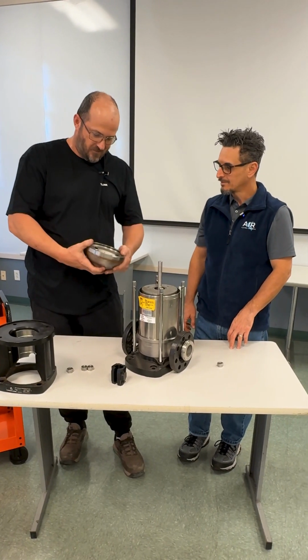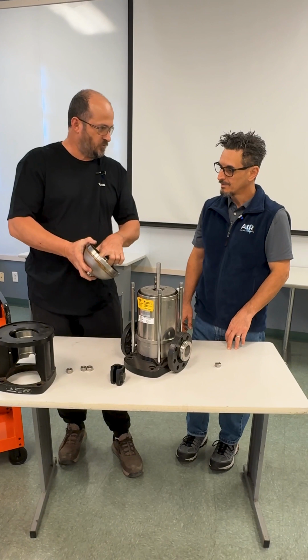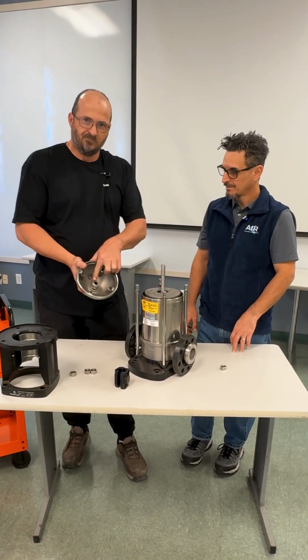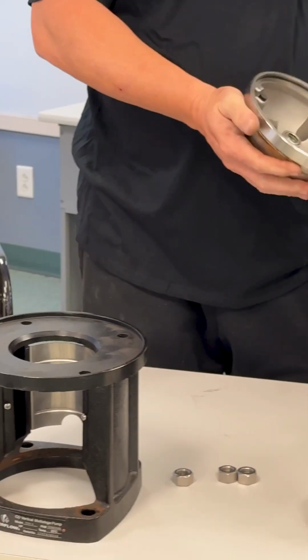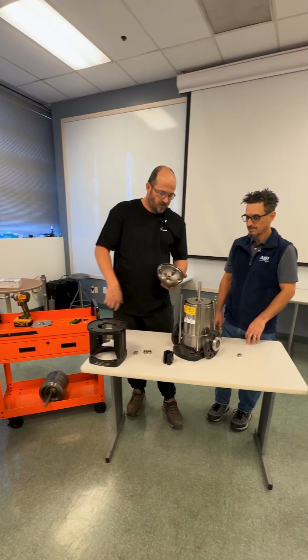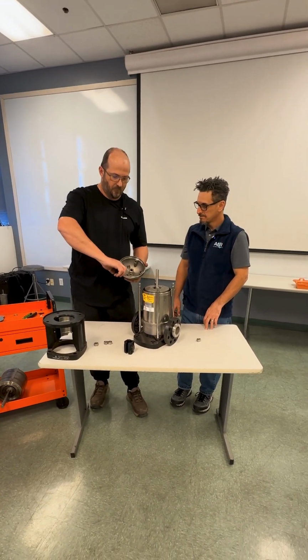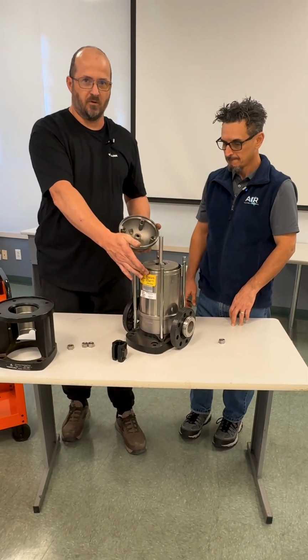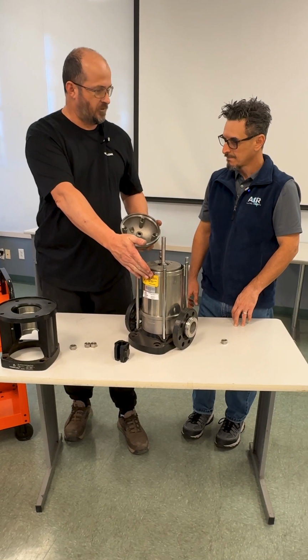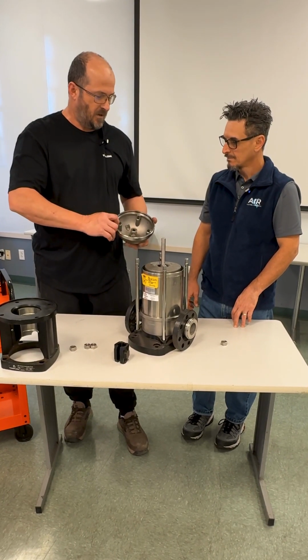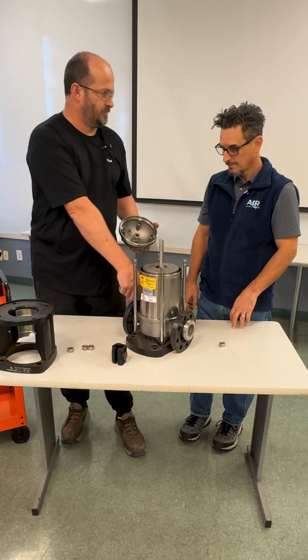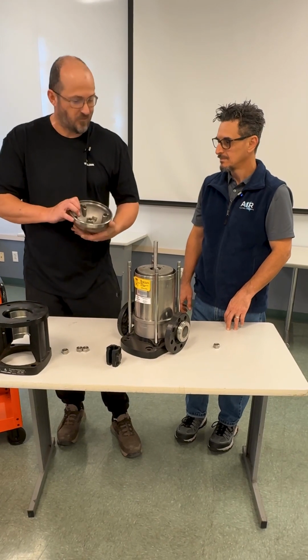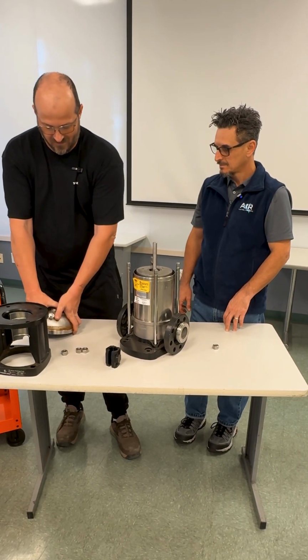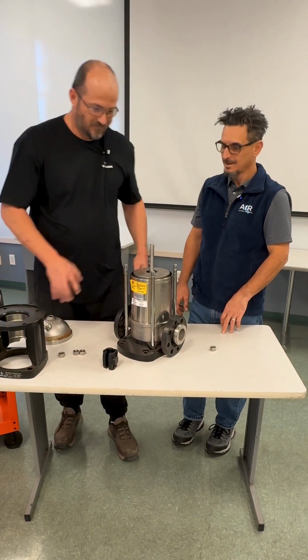Correct. So there's the inside portion of your mechanical seal. Okay, and this is what we call a pump head. Got it. This has an O-ring on it, EPDM, that seals between the outer casing and the pump head. There's also another one in the base. Got it, I've never taken one apart that far unless I had to. Right.